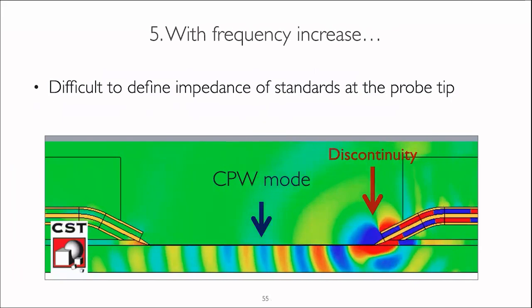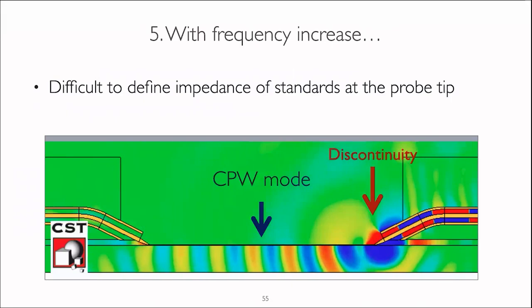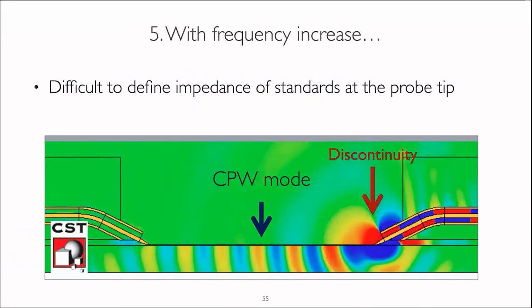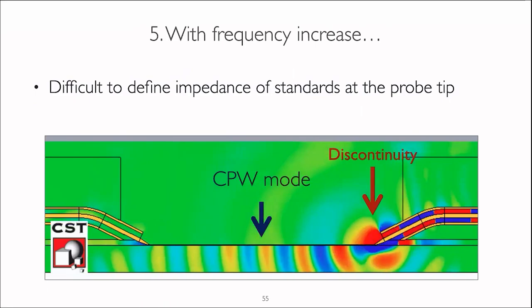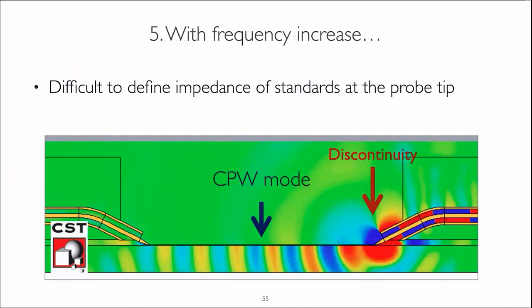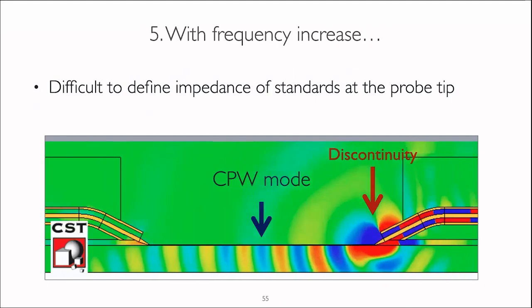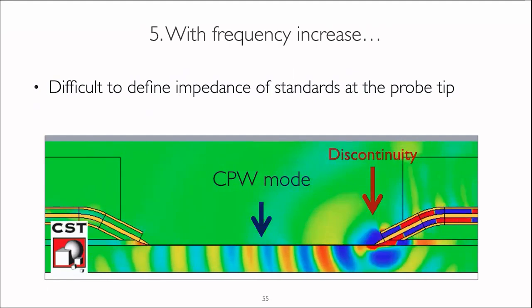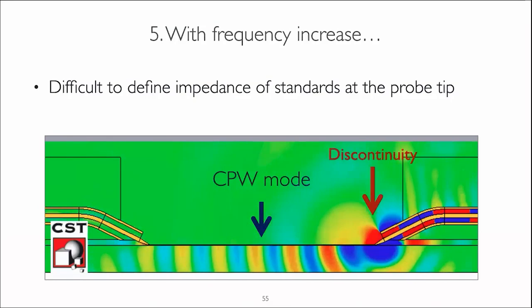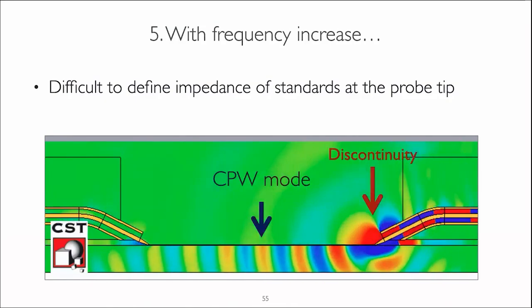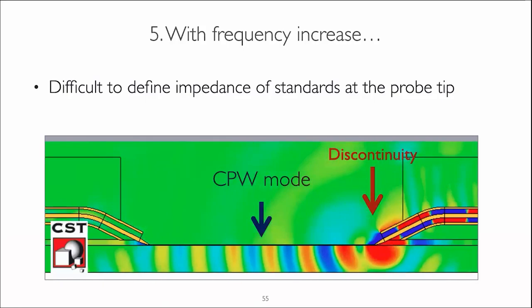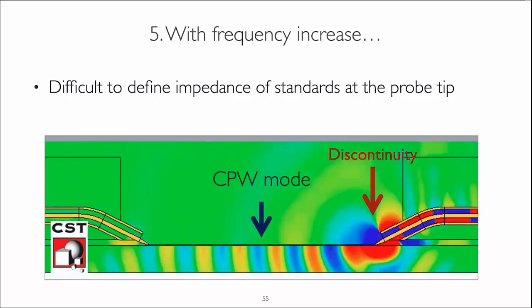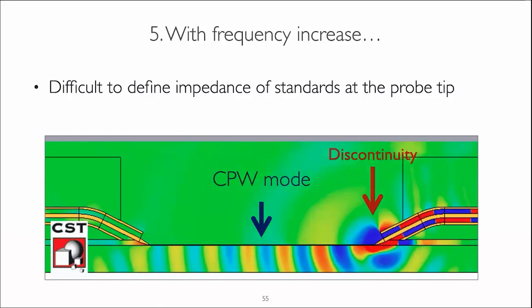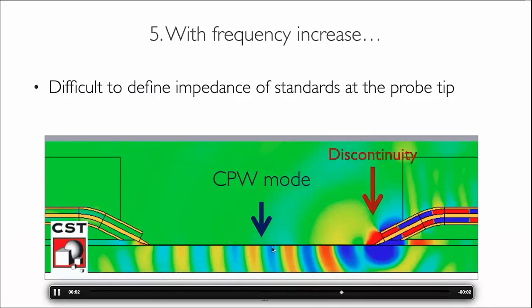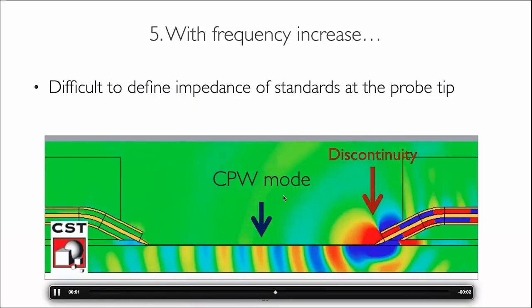Another thing that happens with the frequency increase is that it becomes very difficult to define the equivalent impedance of a planar calibration standard when it is located at the probe tip. Why is that? Because the probe tip is a discontinuity point where electromagnetic waves are not formed properly. And it's always very difficult, if you have a superposition of electromagnetic waves, to define the equivalent impedance of the standard. To which mode do you define it? So we actually don't know. And what you can see on this graph is that the coplanar waveguide line mode is well formed only at a distance far from the transition point.